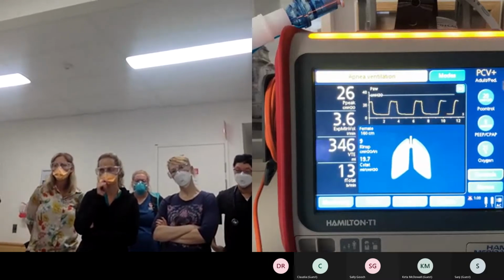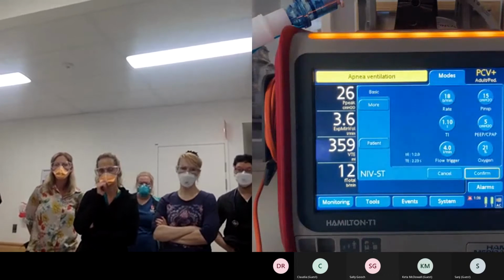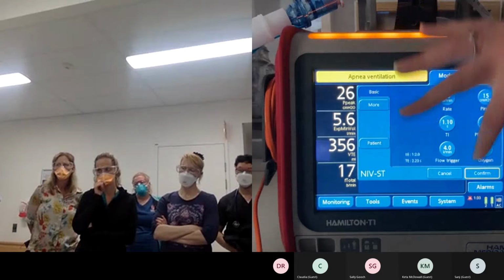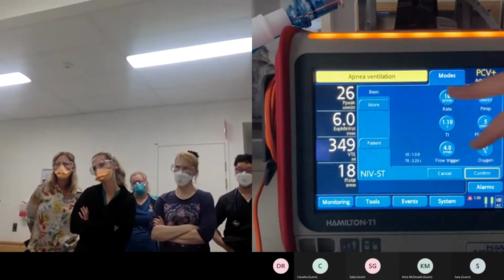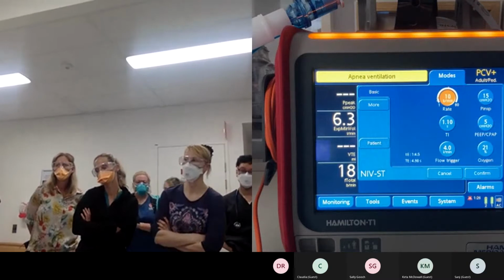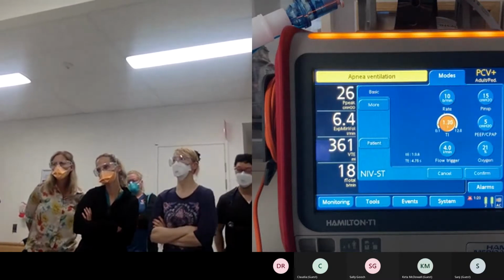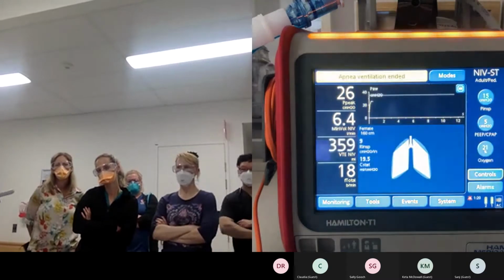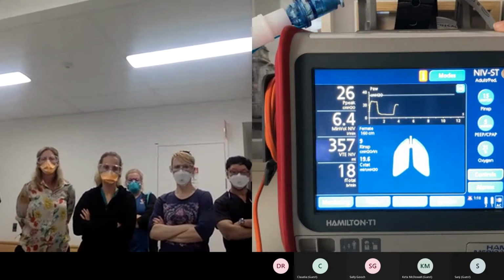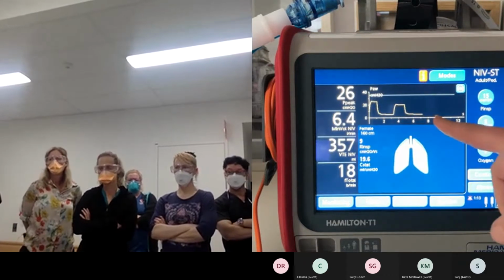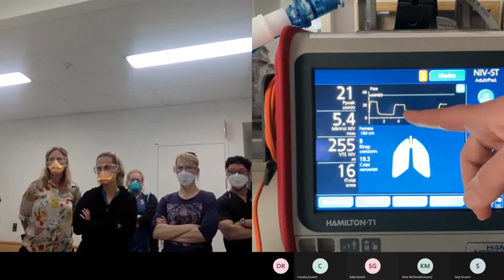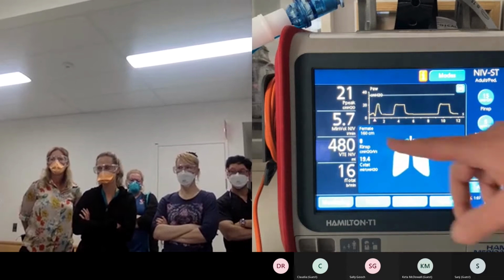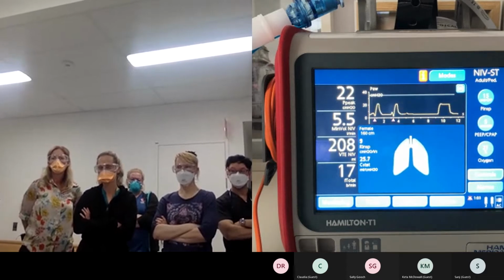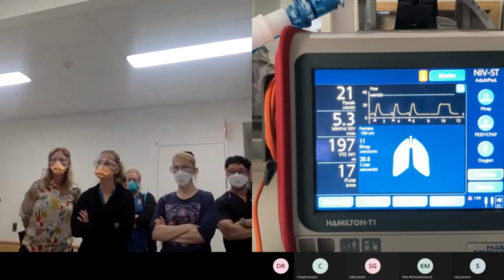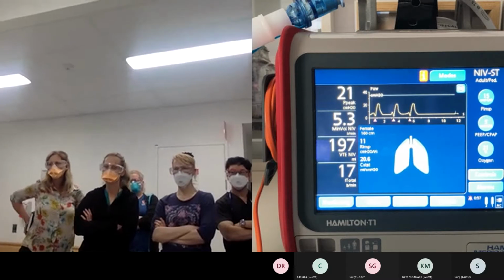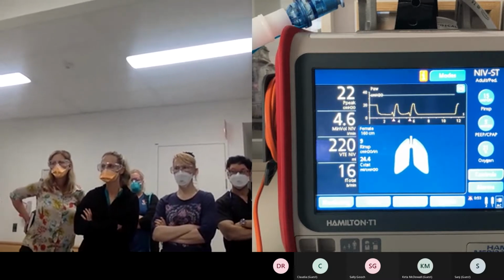Whereas if you were working in NIVST, you can see here that you've still got those pressure and PEEP that run the same. So PSP is on top of PEEP. You set a rate. I'm going to set it at 10. And so you can see here now we're in NIVST, and it almost looks a little bit like that PCV. So it's delivering breaths. If your patient was breathing, you'd see the triangles and there'd be spont breaths. If the patient doesn't trigger a breath, it delivers one of those mandatory breaths for you. But you're not made aware.